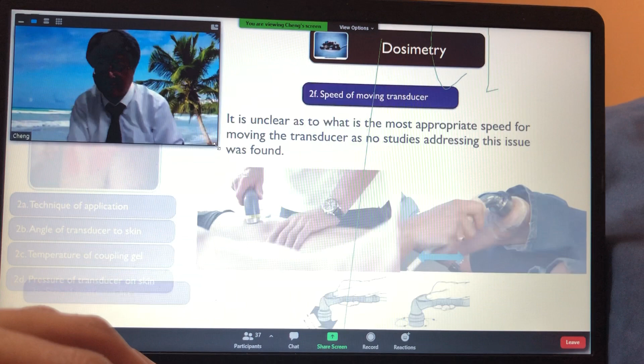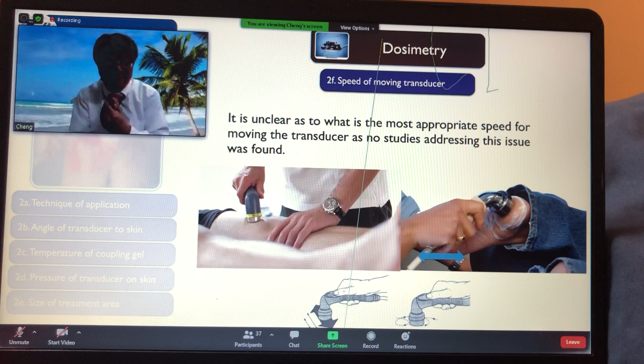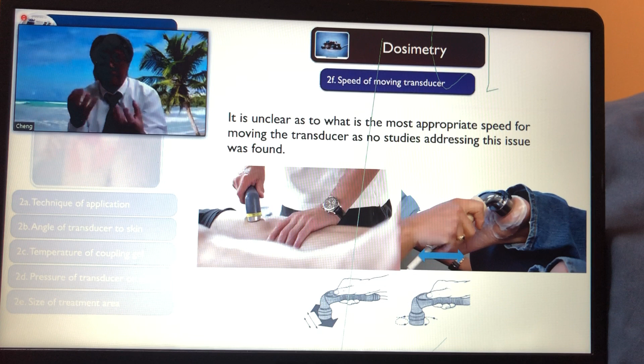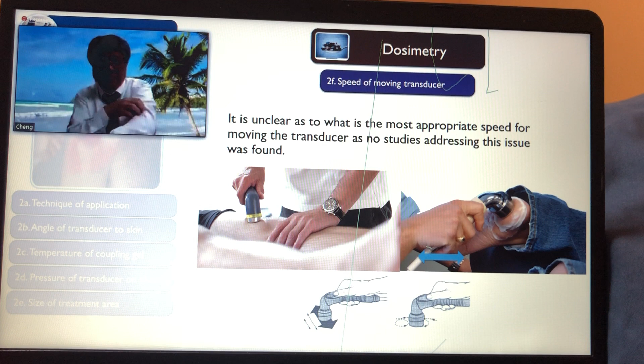So the next one is speed of moving the transducer. Does speed matter? Some of you probably will say yes. In workshops, they always say, yeah, it matters. Why? Because if I slow down, they start to get hot. If I move faster, they don't feel so hot anymore. That's just the hot spots that you're talking about. So that's probably a bad transducer, something that has a very bad BNR. But with a normal BNR, the speed, whether you're slow or fast, should not give you hot spots.